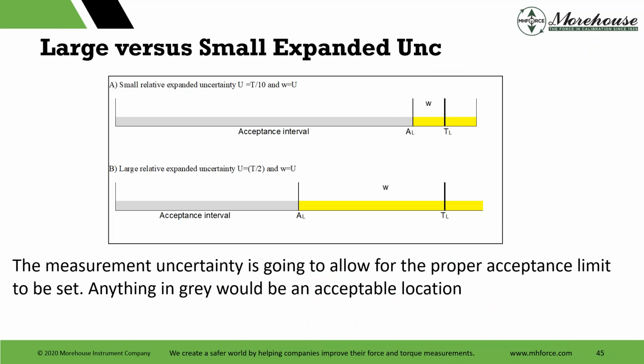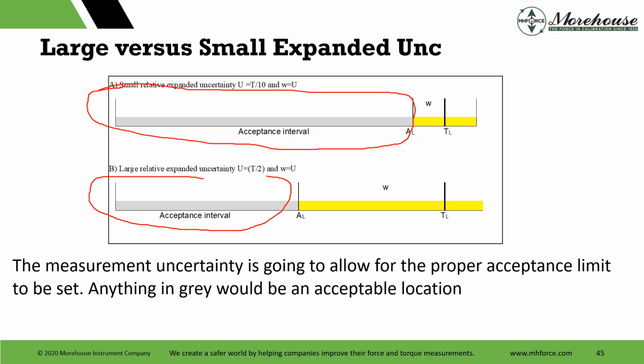Large versus small expanded uncertainty. Here's what we're talking about. When you have a small relative span, you have much more room to be in. Look at this acceptance interval. Remember the primary standards at 0.002%, we look at those versus secondary at 0.01, and then you get a much smaller interval. And that's what we were just showing. So the lab with the better measurement process uncertainties, the better capabilities, is going to have a much larger acceptance interval to call your devices in tolerance.